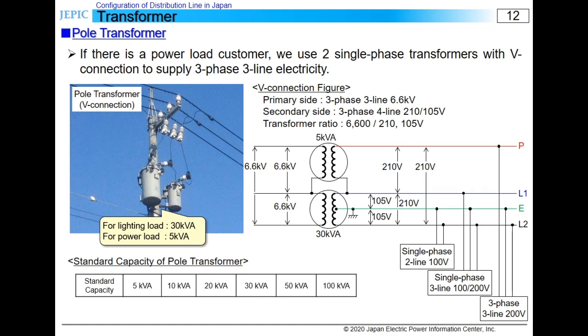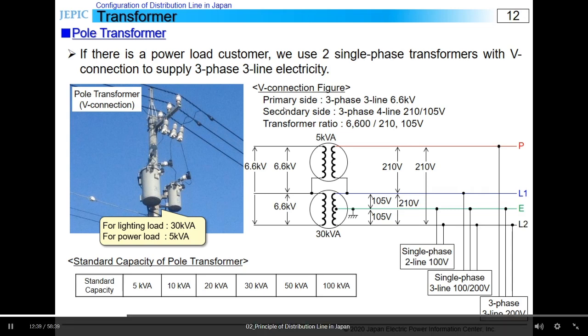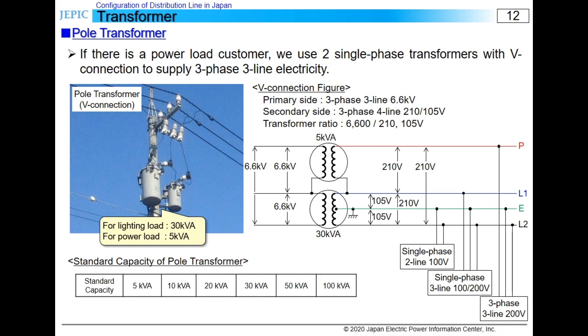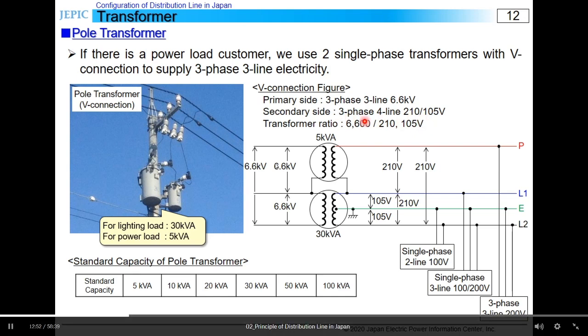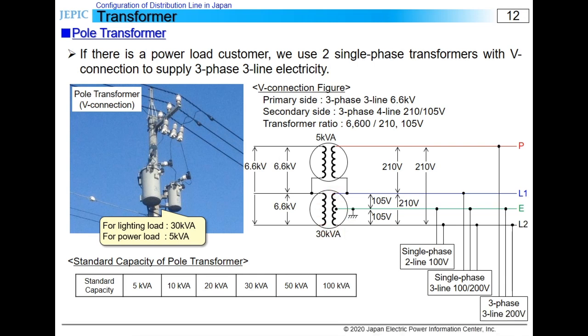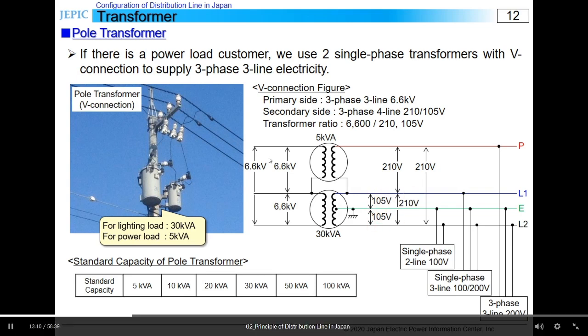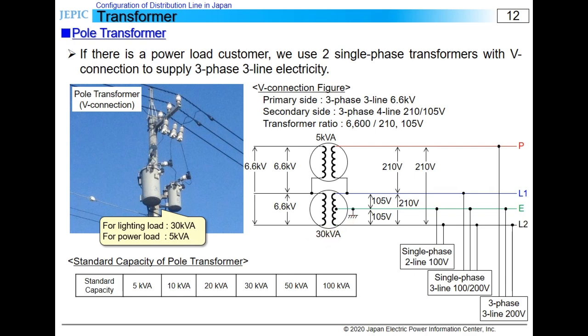As I explained before, 6.6 kV is mainly used for the high voltage distribution line, and 100 or 200 volt is used for low voltage. The transformer ratio is usually 6.6 kV to 210 or 105 volt, and as shown in the figure, at the low voltage side, a transformer has three terminals. One of the terminals comes from the middle of the secondary coil so that it can supply a single-phase line. And also, the two transformers might have different capacities, but the same specification.